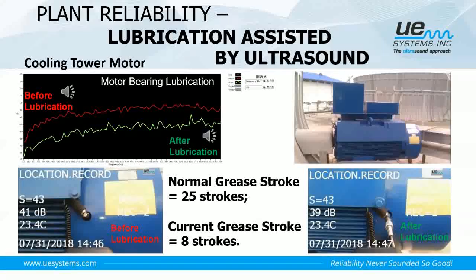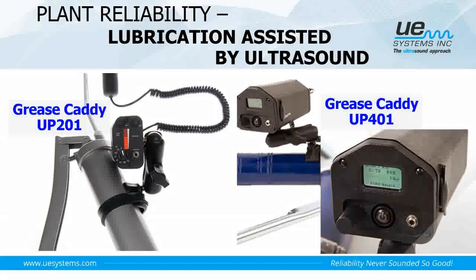So the grease nameplate is just a reference for everybody. Still, we need to grease according to the needs of the bearings. UE Systems offers two types of grease caddy for bearing greasing: the UP201, an analog device with LED indication, and the UP401 with digital dB value display.